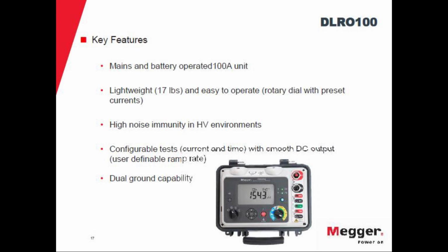Yes, so basically for any breaker below 100 amps, you need to test with lower current. Okay. So if you're testing a 20 amp breaker, you don't want to go past 20 amps. You dial this thing down. Yes, because first, it's like 10 or something. Exactly, because everything in the breaker will start heating up because of that high current. You are exceeding the nominal rating of the breaker. Okay. Now, if it is for something else, not a breaker, basically just consider any nominal current or rating that it has, because if you have higher current, it will heat up that sample. Okay.